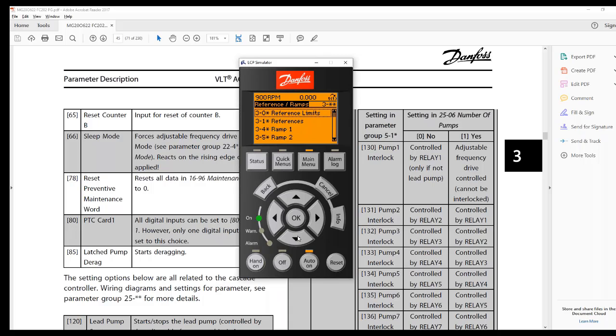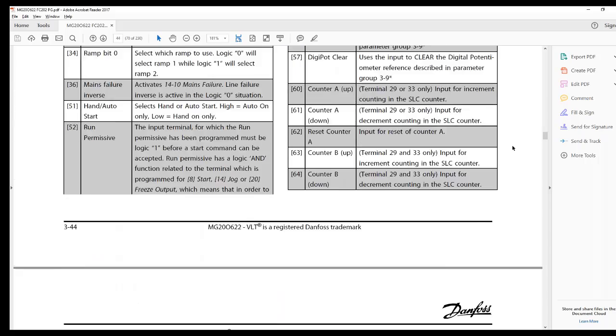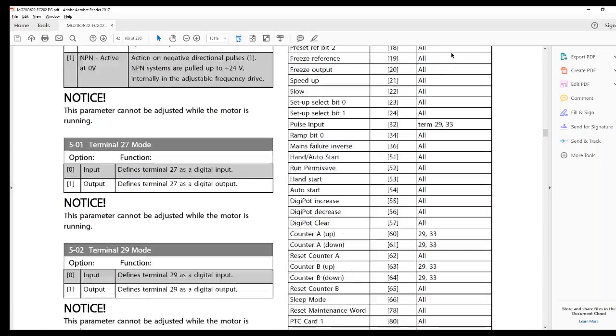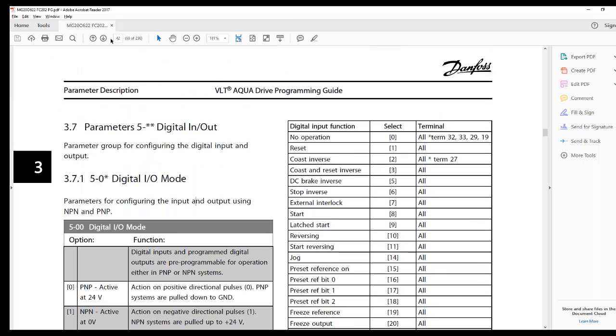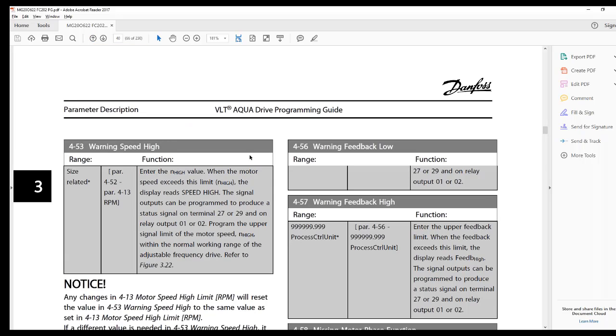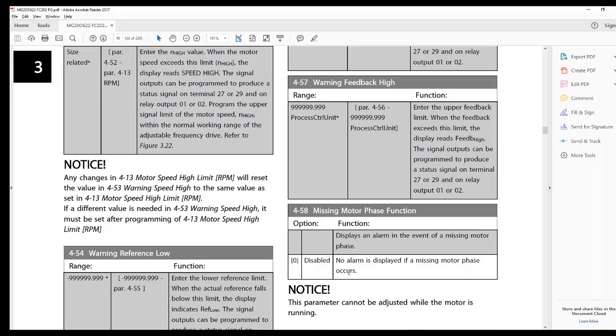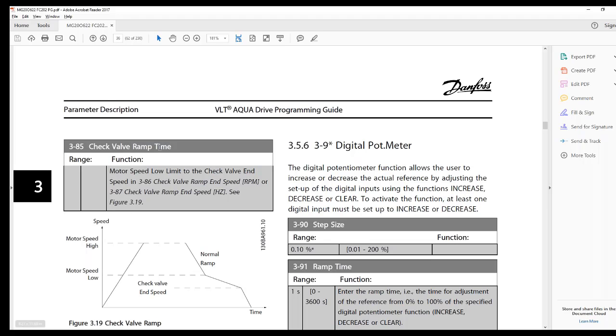And if I look at the ramp times of the FC202, we do have our main ramp up and down times, as well as for certain pumps, we have other ramps which will be part of this also. There's an initial ramp, so this is one for certain pumps that can't ramp up slowly, you need to get up to a minimum speed quickly. And for a better view of that, for programming any drive, I take a look at the programming guide, and this is a guide that has every parameter, every description, including the DERAG and how to tune it is in here too. And there are good charts telling you what all these functions are.